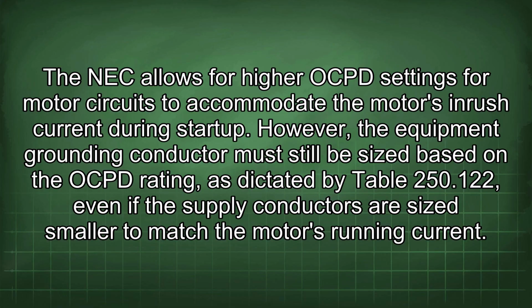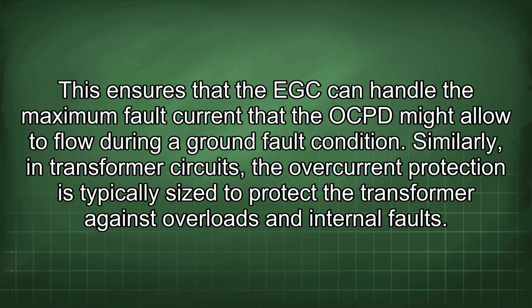However, the equipment grounding conductor must still be sized based on the OCPD rating as dictated by Table 250.122, even if the supply conductors are sized smaller to match the motor's running current. This ensures that the EGC can handle the maximum fault current that the OCPD might allow to flow during a ground fault condition.